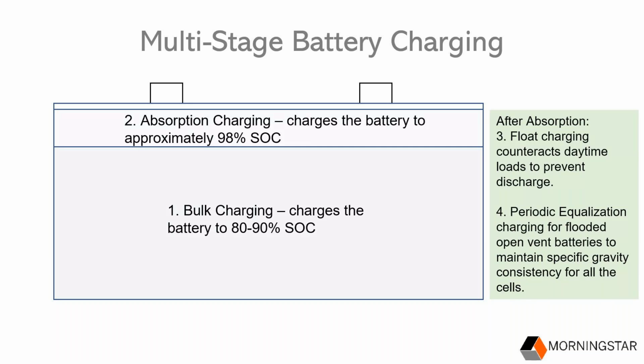For flooded open vent batteries, an equalization charge is applied once every 2 to 4 weeks to maintain consistent specific gravities amongst the individual battery cells. The more deeply a battery is discharged on a daily basis, the more often equalization charging is required. Now, it's important to note that equalization is for flooded, not for sealed, gel, or valve regulated batteries, which can be damaged by equalization. It's also very important to note that this slide pertains to lead acid batteries only. Other battery chemistries can have very different charging requirements.